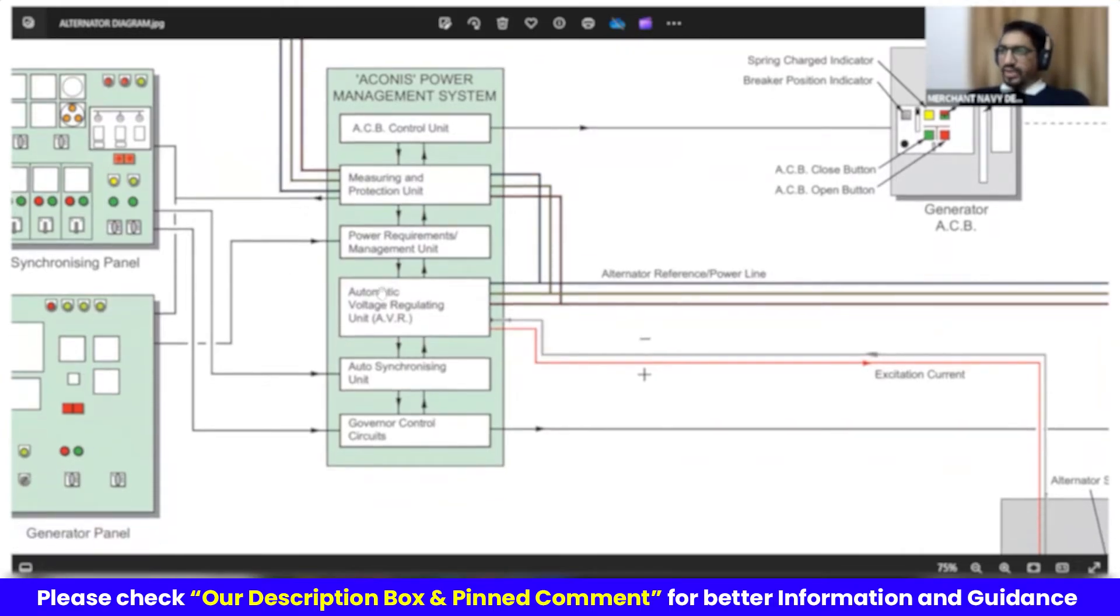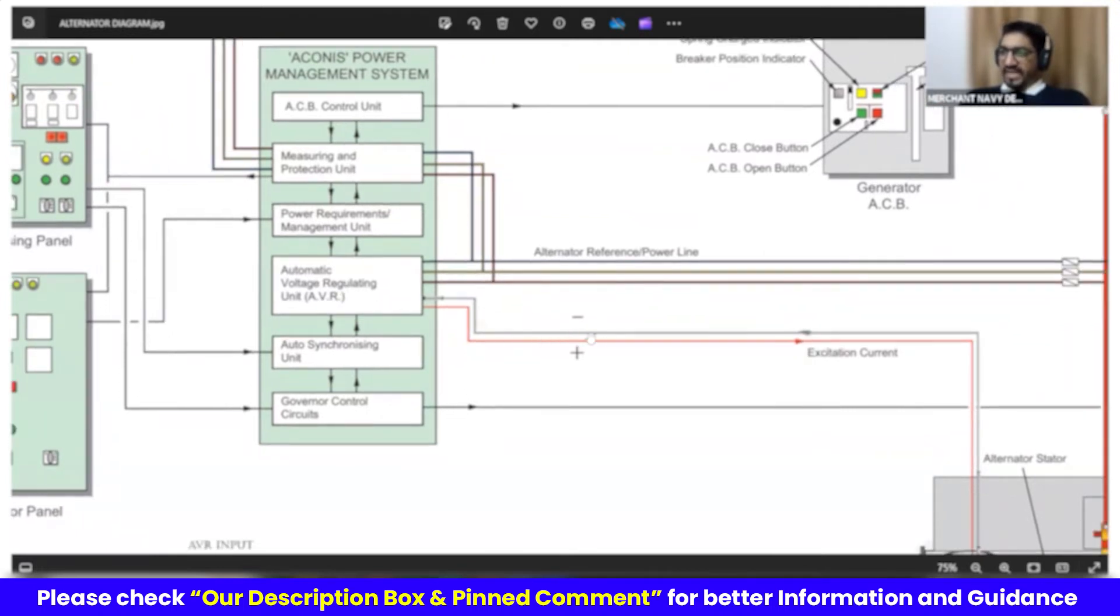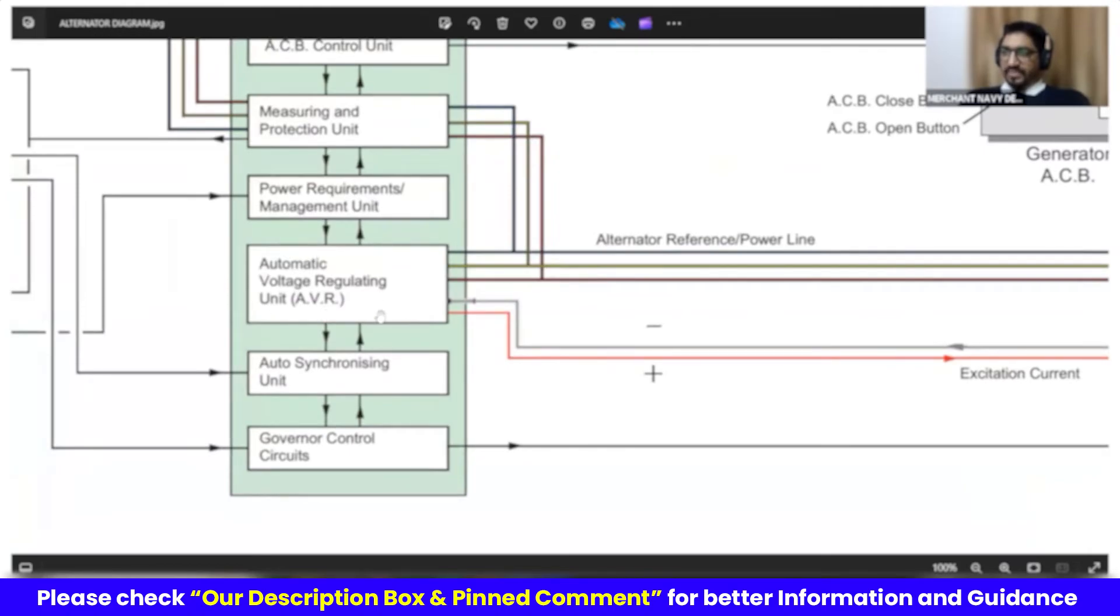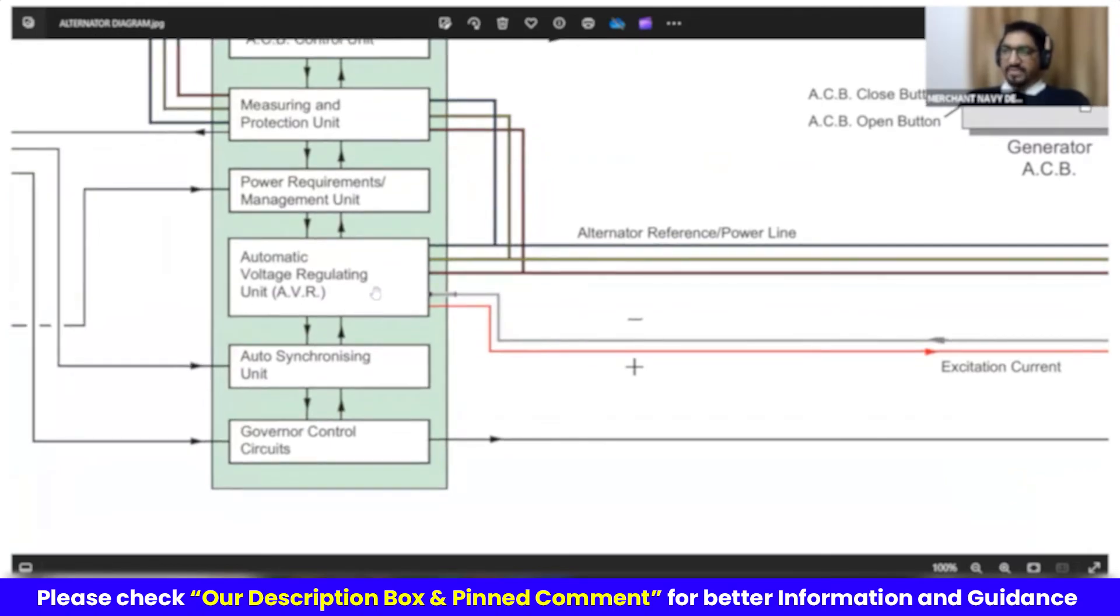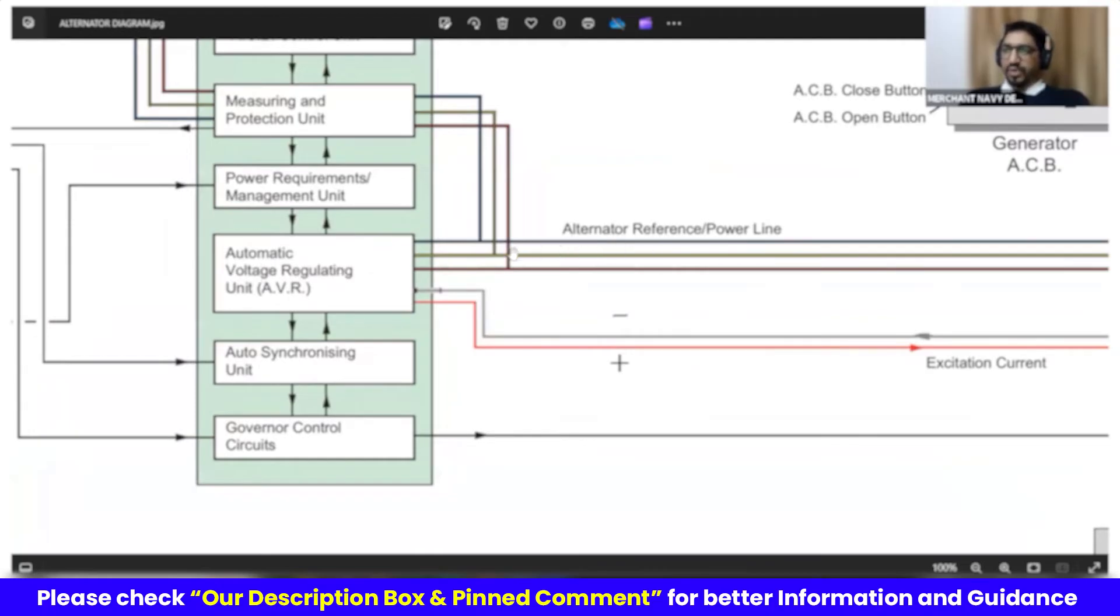Also, it is going to AVR. This is for control part. Measuring and protection is different from control. Control is basically to check if it is 440, then fine. If it is less than 440, a DC output from the AVR needs to be changed. This is an AVR, which is inside the main switchboard. Sometimes it is in the generator also, alternator. It is part of MSB, main switchboard.